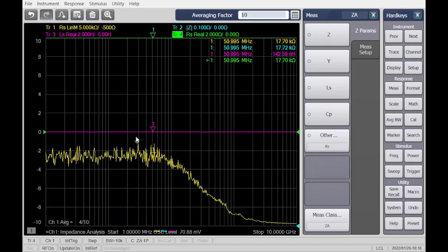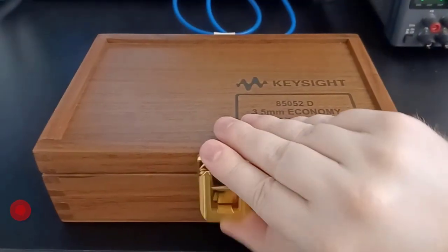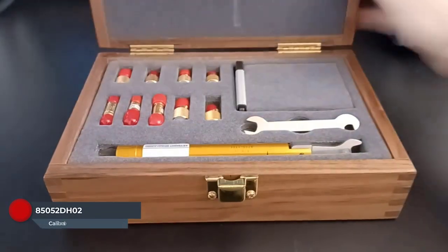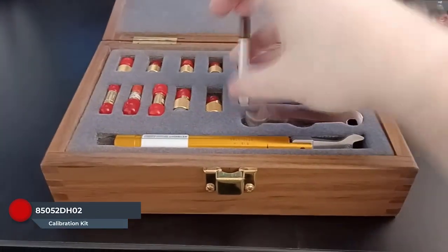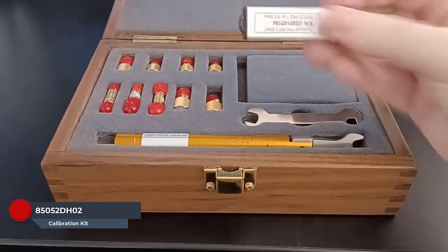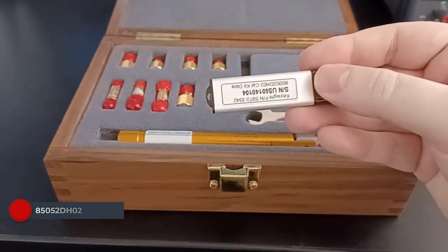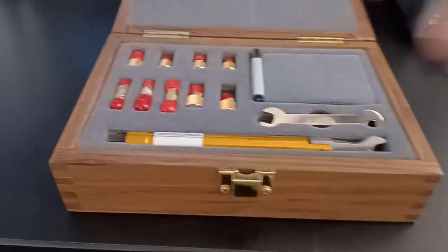Prepare to calibrate the system. This requires the use of a data-based cal kit, the 85052DH02. To use this kit, import the data from the cal kit's provided file.